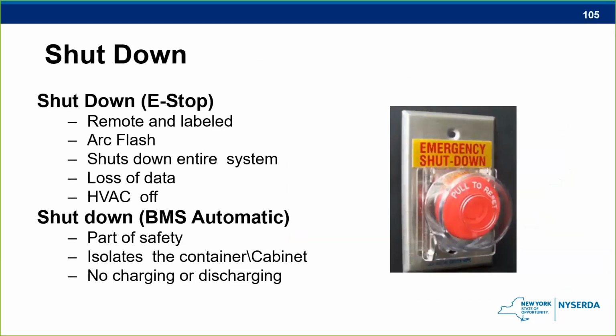The shutdown. We said before, when firefighters are shutting these things down, if there are some installations that have more than just one enclosure, maybe it has 90 enclosures, is that shutdown system actually shutting down all 90 enclosures, or is it just shutting down the one enclosure? And this is where the AHJ has to take a look at that electrical connection to see how they're doing it. And if that emergency is for the whole system, well, in the event of an emergency with no fire showing, maybe we just had a cell go bad, but the system continued to operate perfectly, do we want the responders actually shutting that thing down unnecessarily? So this is where the education comes into the firefighters. We don't want them shutting that thing down unnecessarily.